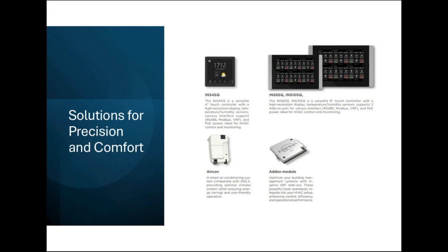It also communicates with the Modbus HVAC system directly. So to club it with iNELS, you can use the iNELS add-on module plus this VRF add-on module, so you can work the iNELS system and the VRF system together. Or you can use MQTT to connect to the Inspinia screen and then connect the VRV module and then communicate with the HVAC system. This is one way.